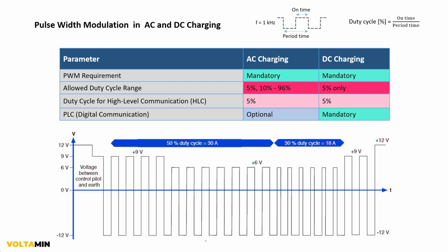For AC charging, the duty cycle ranges from 10% to 96%, with each percentage corresponding to a specific maximum current the EVSE can provide. For instance, a 50% duty cycle represents 30 amps, while a 30% duty cycle corresponds to 18 amps. A fixed 5% duty cycle is used for high-level communication, HLC, as per ISO 15118 or DIN SPEC 70121 standards. In DC charging, the duty cycle is consistently fixed at 5%, with communication handled via power line communication, PLC. PLC supports advanced digital features like initiating charging, monitoring battery health, and safely managing power delivery. Unlike AC charging, PLC is mandatory for DC systems to ensure secure and standardized communication.